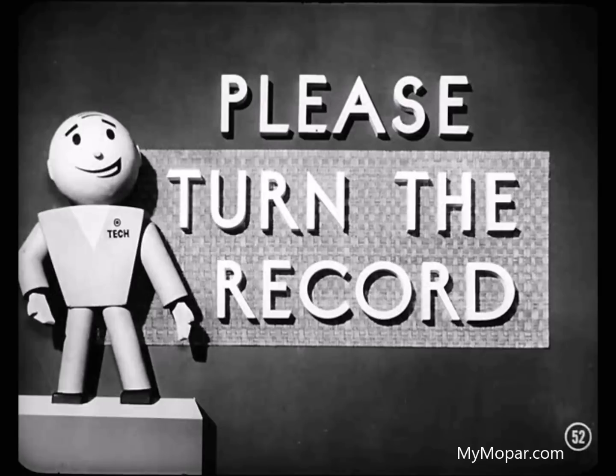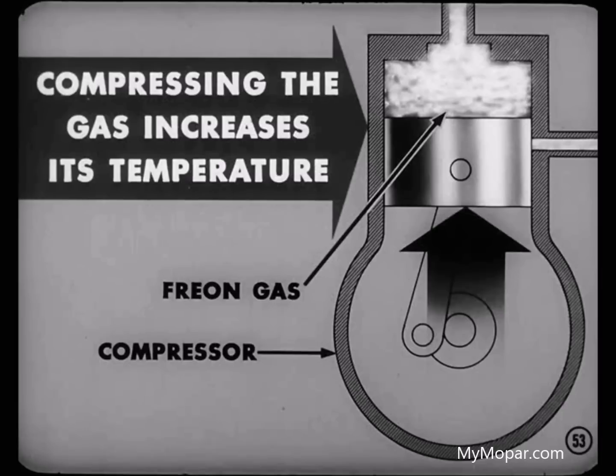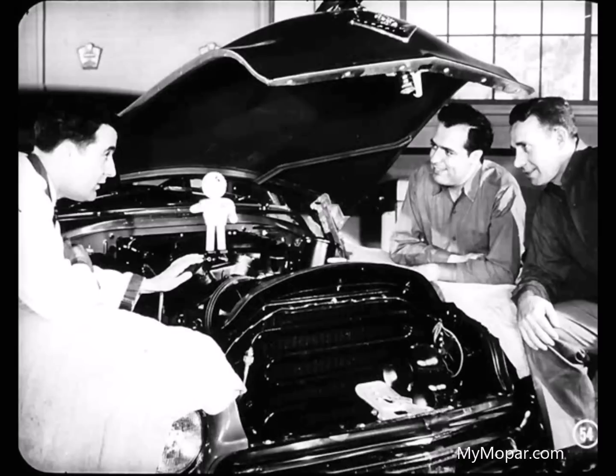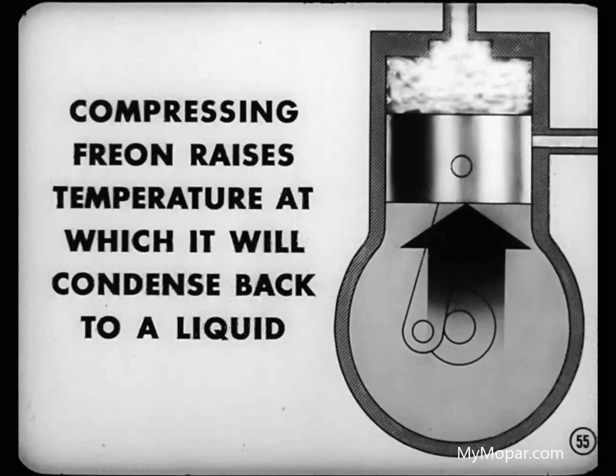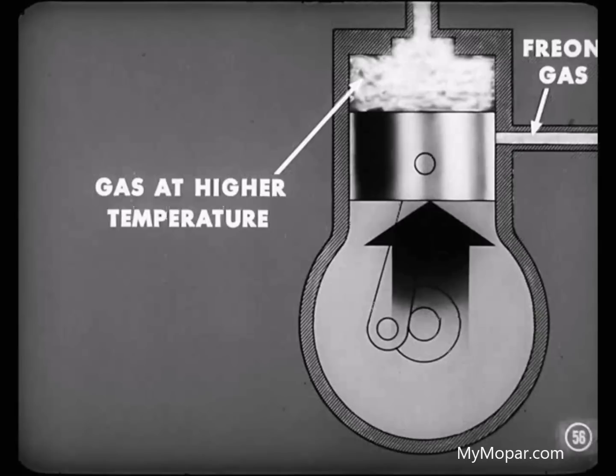Now we're all set. About that compressor, Bill — its job is to build up pressure on the Freon gas. Remember, by compressing a gas, we increase its temperature. In fact, the temperature of the Freon gas goes up so high it can be cooled at summer temperatures. And this brings us up to another phase in the operation of the system. Compressing the Freon raises the temperature at which it will condense back into a liquid, and this is done by the compressor.